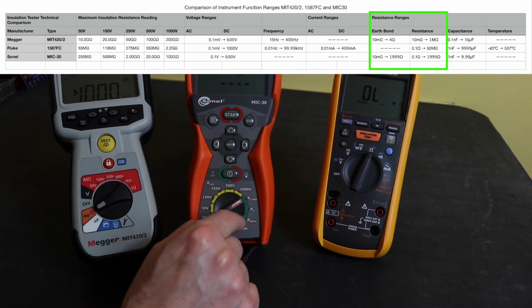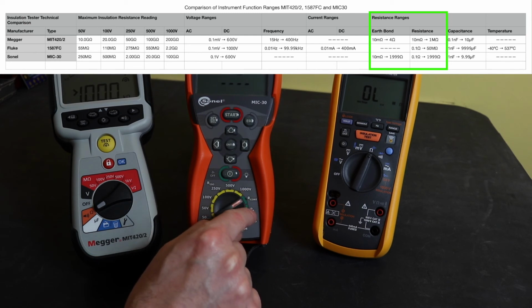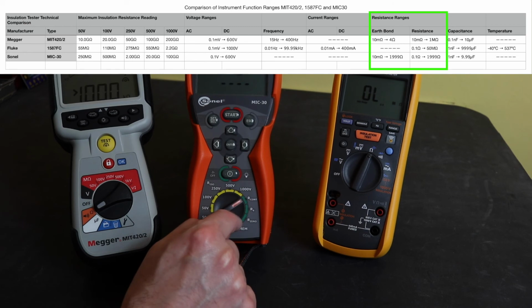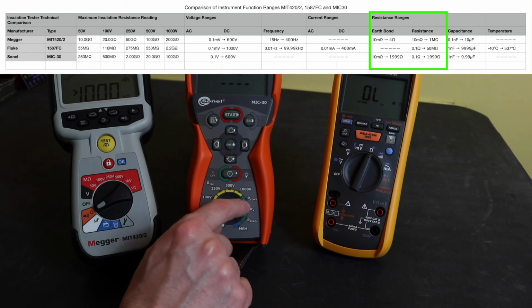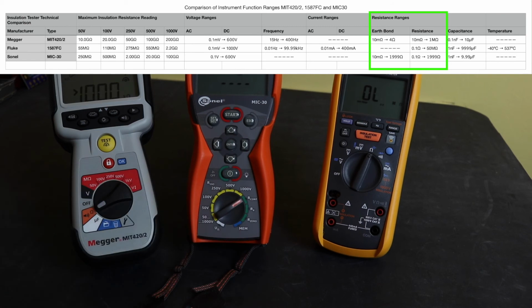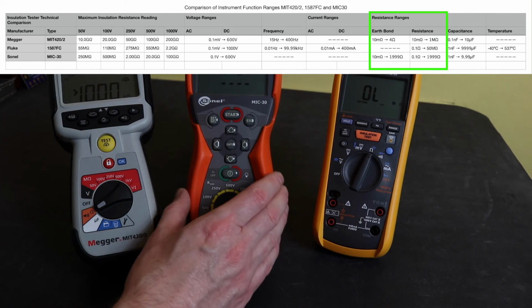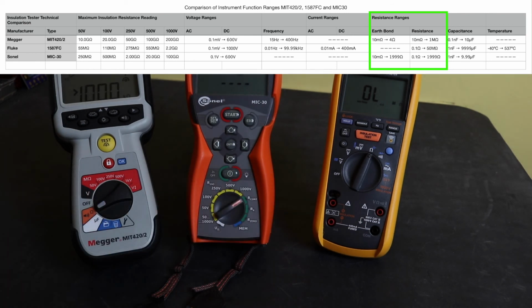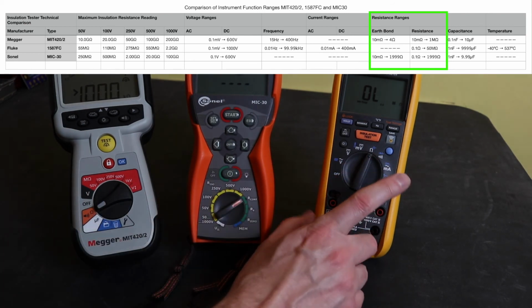For the Sonel here, the continuity and the resistance reading are split across these two functions. Only the continuity has a 200 milliamp test, but both functions will only operate from 0.1 ohms up to 2 kilo ohms, so quite a reduced resistance reading capability on the Sonel there.